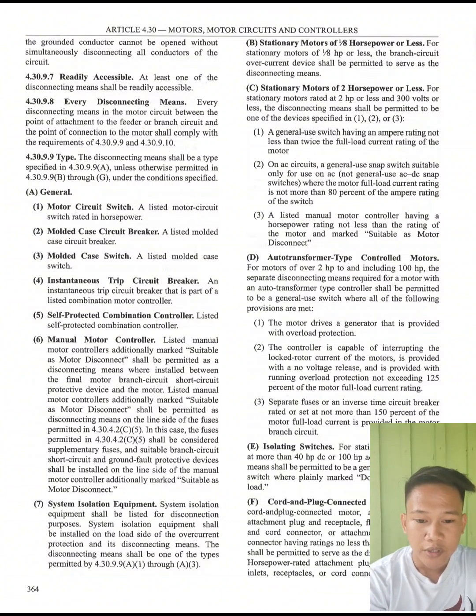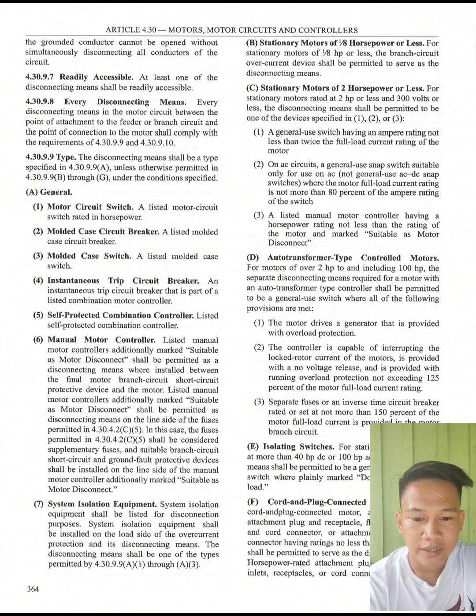General. So first, motor circuit switch. A listed motor circuit switch rated in horsepower. Second, molded case circuit breaker. A listed molded case circuit breaker. Third, molded case switch. A listed molded case switch. Fourth, instantaneous trip circuit breaker. An instantaneous trip circuit breaker that is part of a listed combination motor controller. Fifth, we have self-protected combination controller. Listed self-protected combination controller.